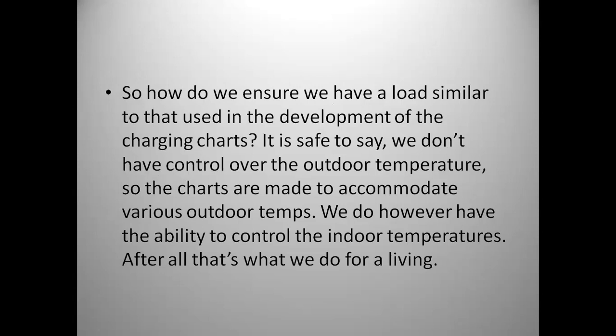It is safe to say we don't have control over the outdoor temperature, so the charts accommodate various outdoor temperatures in both heating and cooling. We do have the ability to control the indoor temperatures. That's what we do for a living. So if it's super cold inside, if it's 60 degrees in the house, it's going to be difficult for you to charge it in air conditioning. So as far as Rheem inverters go, you have the 2 heat pump models. You have the RP17, which is your 3-stage 17 SEER inverter, and you have your RP20, which is your completely variable capacity 20 SEER, and then you also have your RA20, which is your variable capacity inverter AC.